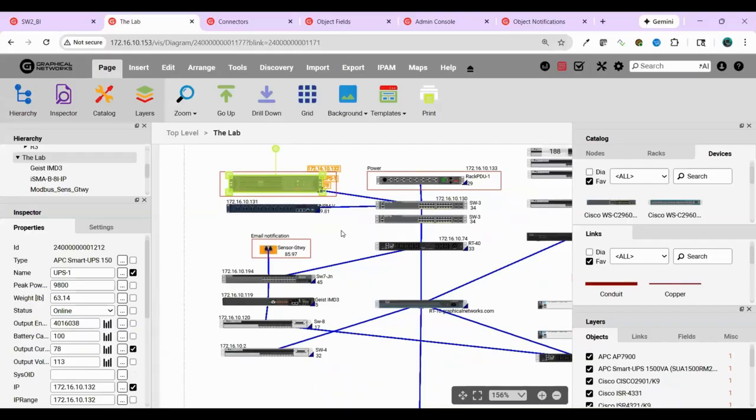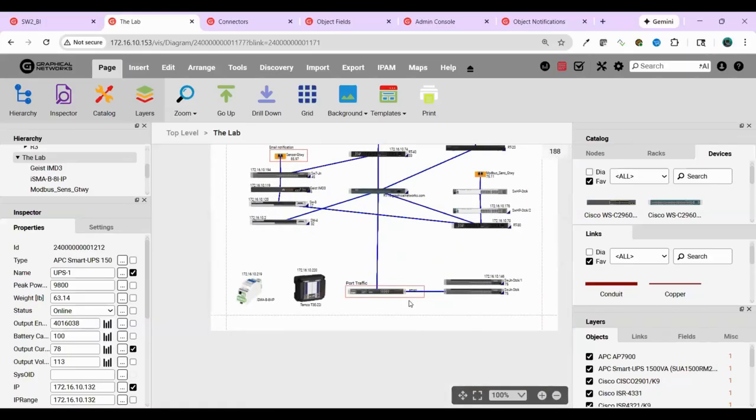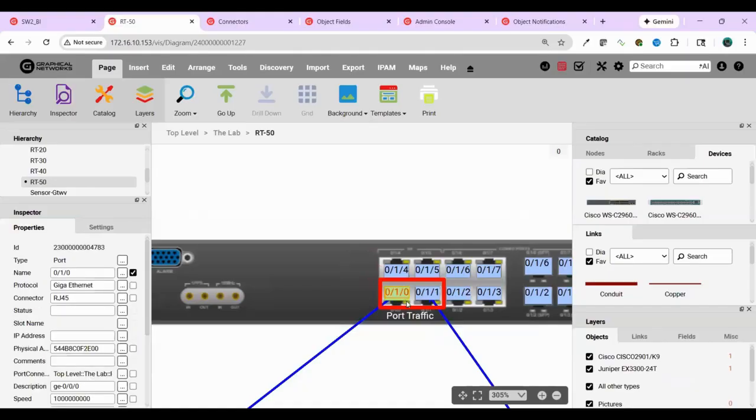Some devices you buy don't have anything. They're not SNMP enabled. But most folks we deal with have devices that are typically PDUs for getting power, again watts or load or current. It depends on what you want to grab data from. As far as a server or a router, you could definitely get CPU utilization. You might get port traffic, so you can get down to the port level on a device.